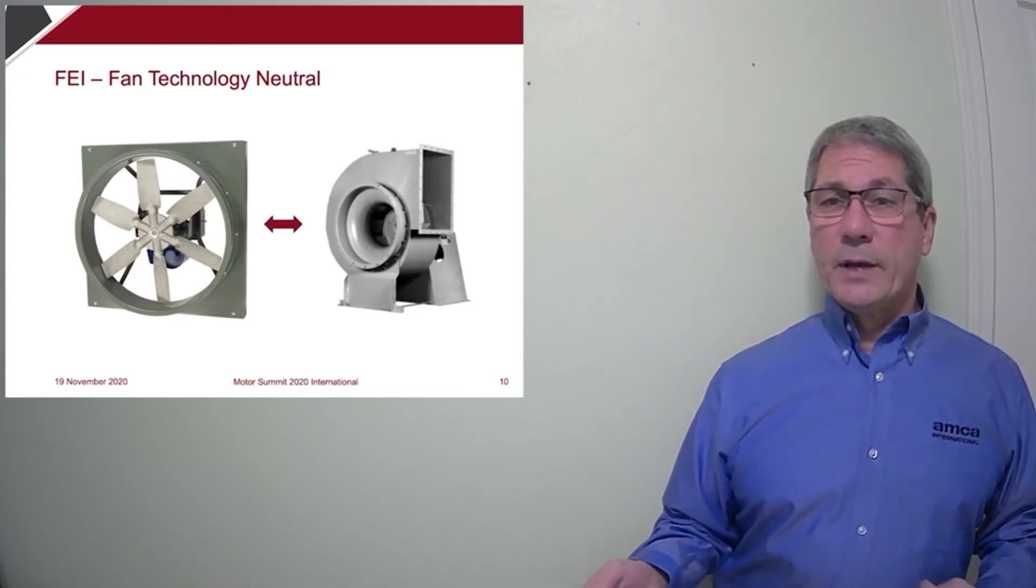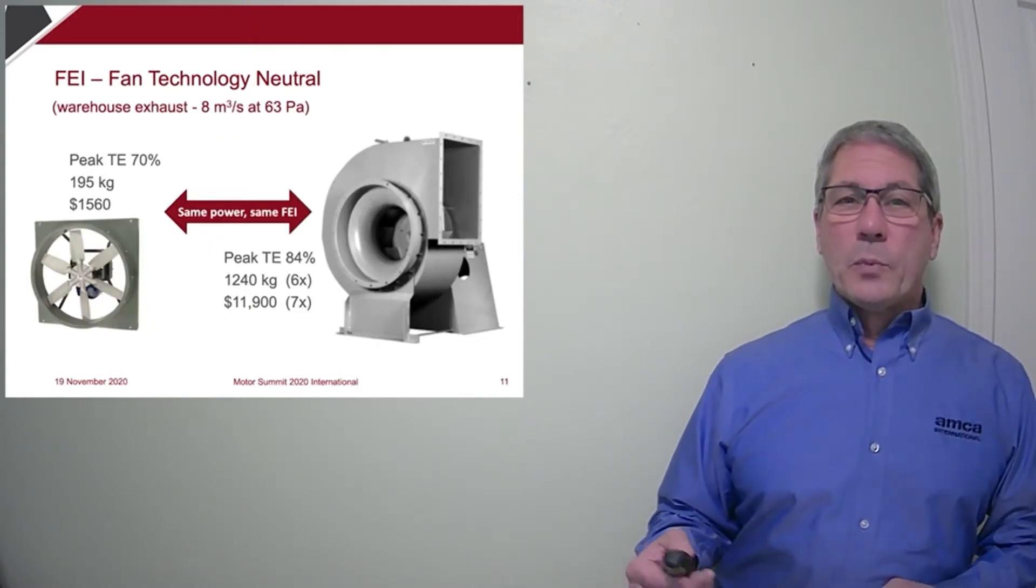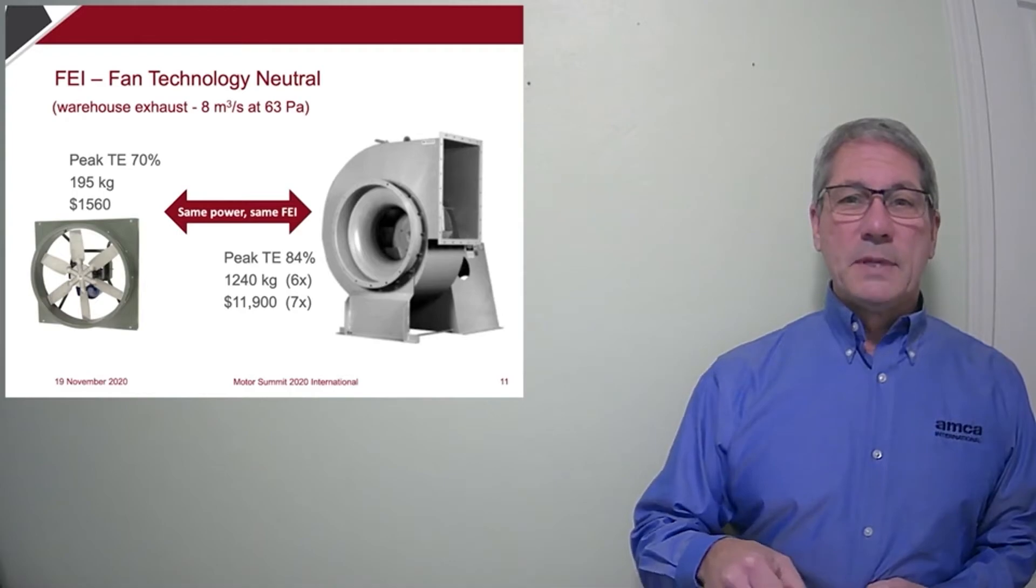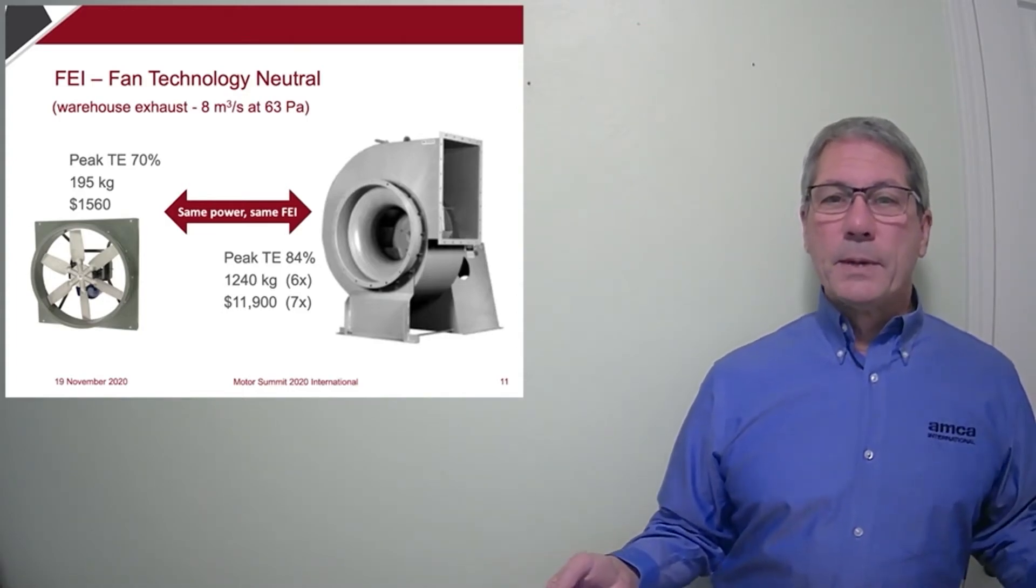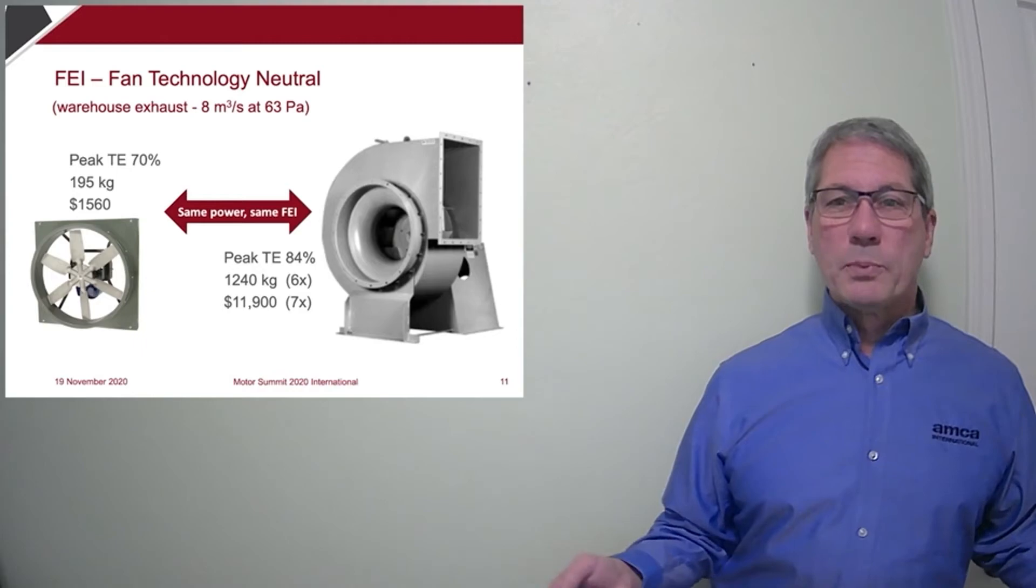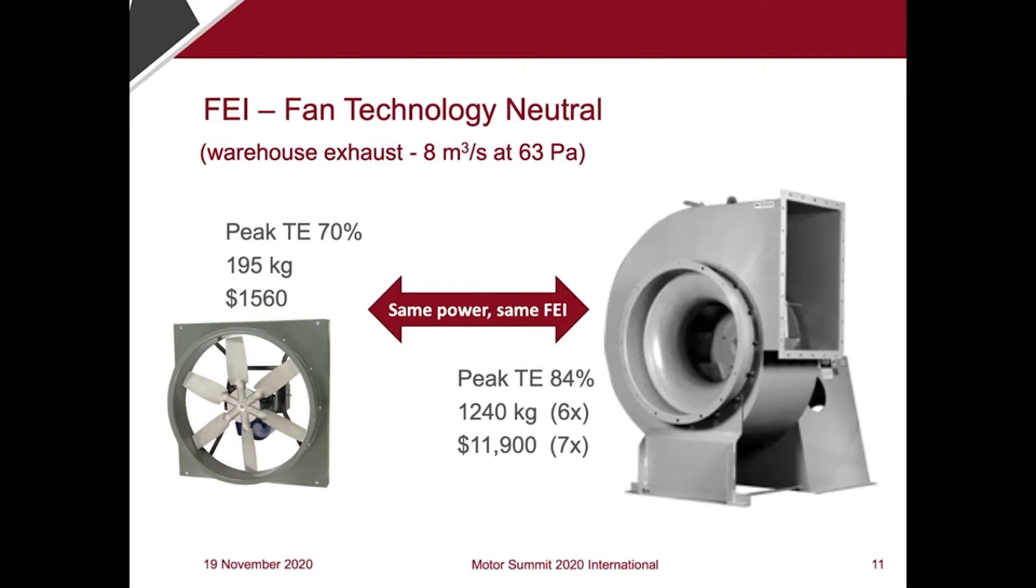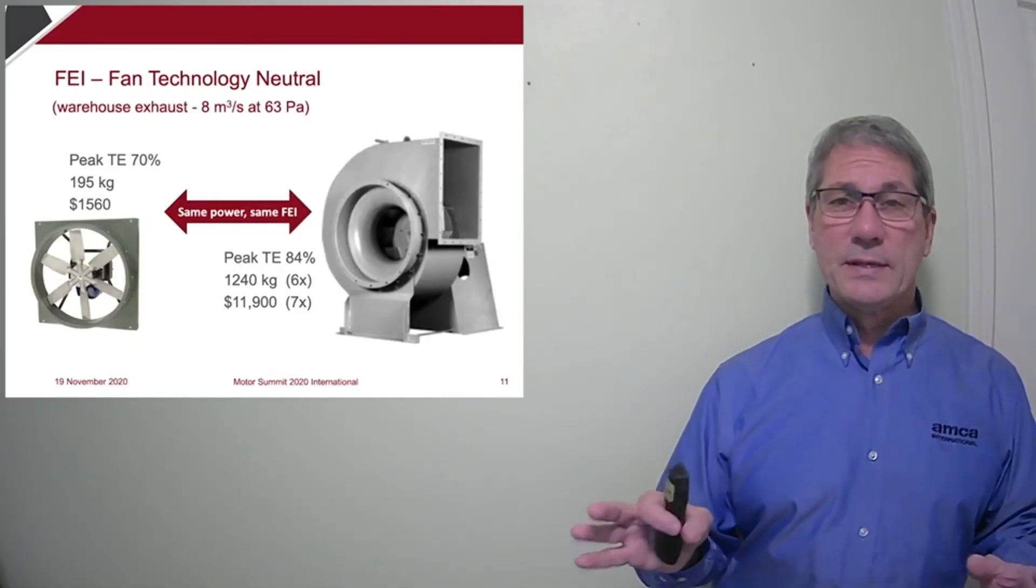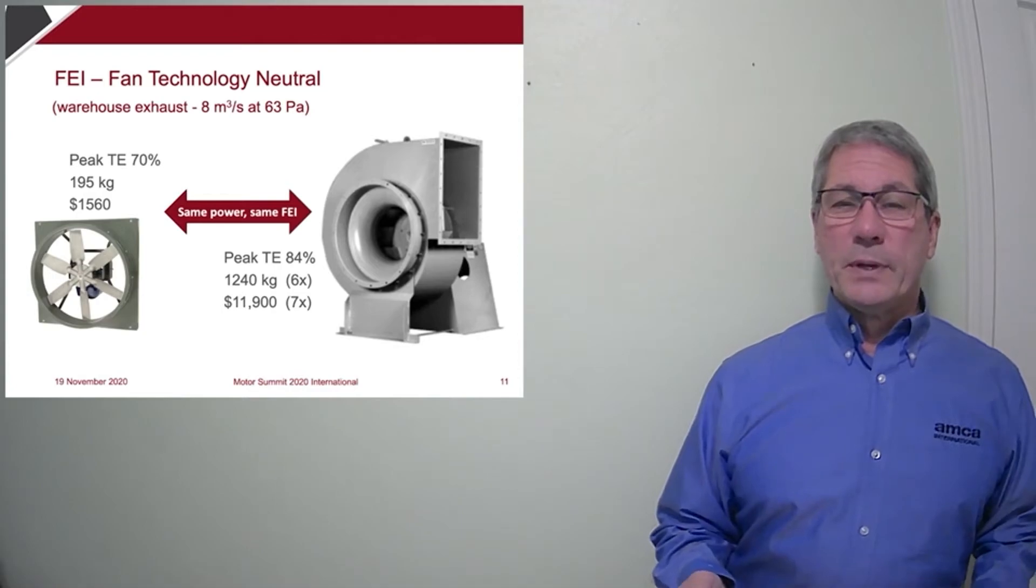The fan with the higher FEI value will have the lower power. But in order for a more efficient product to be substituted, it must actually save energy. An airfoil centrifugal fan is much more efficient than a prop fan. But in a warehouse ventilation application, a low pressure application, the prop fan is the right fan for the job. In order for the airfoil fan to use the same amount of energy and therefore have the same FEI, the size has got to be so large that it would weigh six times that of the prop fan. It would cost seven times as much. And I tried to draw these to scale. FEI is based on consumed power for a given duty point, regardless of the fan type.